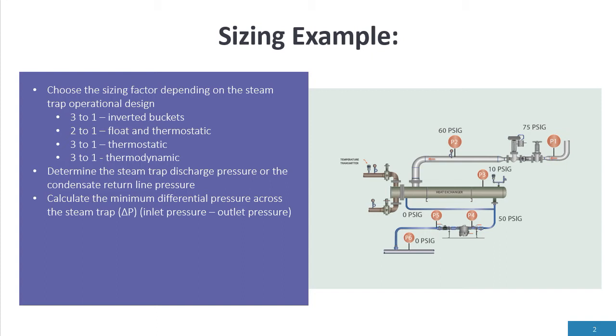For example, inverted buckets are three to one. What does that mean? If my condensate capacity is 200 pounds per hour, then I take three times 200 or 600 pounds per hour. So I want to select the steam trap for 600 pounds per hour in the capacity chart.